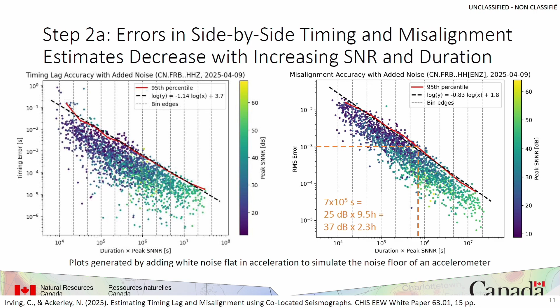What we did was take a high-fidelity broadband signal and degrade it with random amounts of white noise and analyze signals of random duration. So on the right, for any desired level of accuracy, you can pick off the required duration times peak SNR to get the estimated 95th percentile error. So for example, to obtain a 0.1% error, you need 9 hours at 25 dB or 2 hours of 37 dB signal-to-noise ratio.